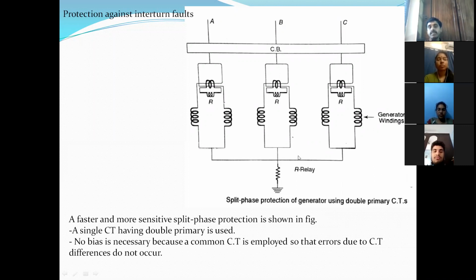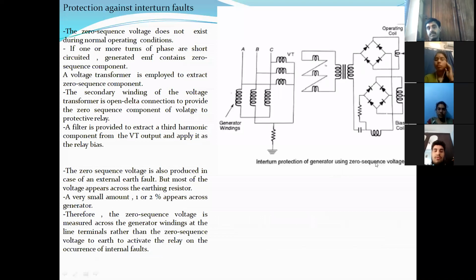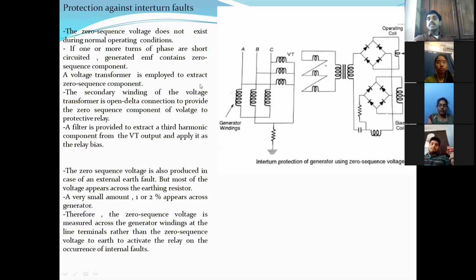So another scheme is zero sequence voltage. Here, one important point to keep in mind is, whenever there is an internal fault, what is the indication? Normally, when there is a phase fault, there is an indication that the current is increased in a particular phase. For internal faults, that means interturn faults, there are some indications. Based on that, we can design a protection scheme. You see, the zero sequence voltage does not exist during normal operating conditions. Whenever there is an interturn fault, there is a zero sequence voltage.